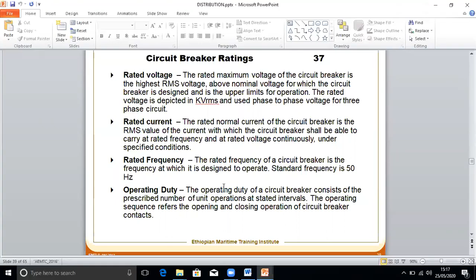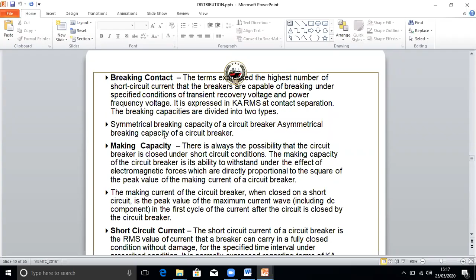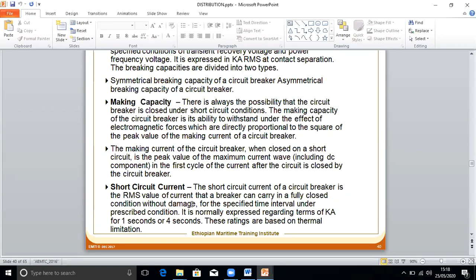Breaking capacities are divided into two types: symmetrical breaking capacity of a breaker and asymmetrical breaking capacity of a breaker. The terms express the highest short circuit current that the breakers are capable of breaking at specified conditions. Short circuit current rating of a breaker is the RMS value of the current that a breaker can carry in fully closed condition without damage. It's a maximum short circuit current. This is symmetrical breaking current. It is the root mean square value of the AC component of a breaking current. That is called symmetrical breaking current.